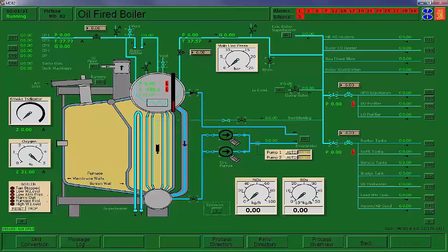We'll go ahead and open our air cock, and this you would close once steam pressure is raised and you see steam coming out of this vent. The air cock is there so that the steam will push out any atmosphere within the steam drum, so that O2 does not get included into your boiler water. We're going to open our de-superheated steam stop 100%.